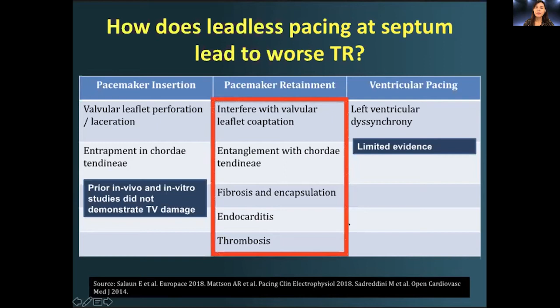When we implant a transvenous lead, we usually focus on positioning the tip of the lead at the appropriate position. However, during the implantation of the leadless pacemaker, the story is a little bit different. Let's look at the diagram on the left. Implantation of the leadless pacemaker is performed using a very bulky device, and we also need to perform a gooseneck maneuver during the procedure. Sometimes this can lead to pushing of the septum slightly.